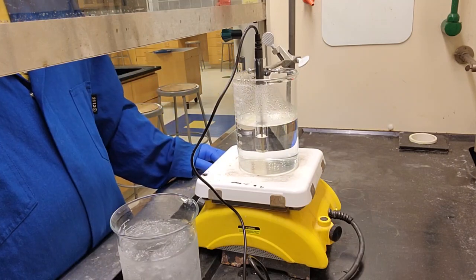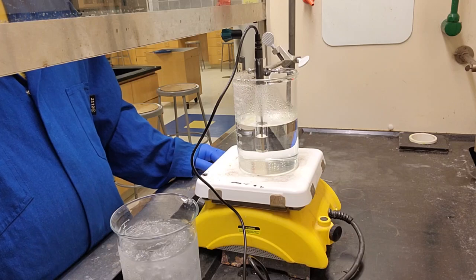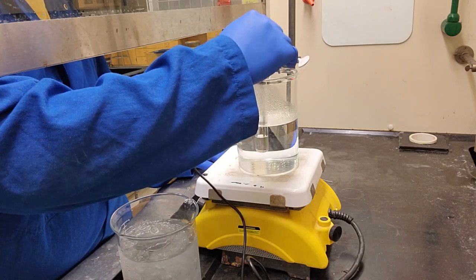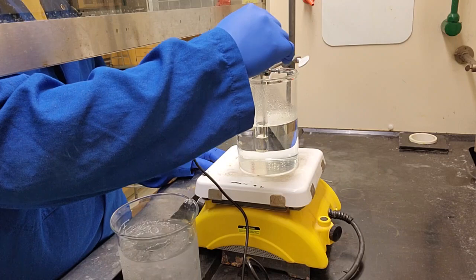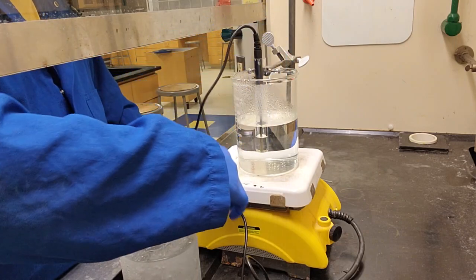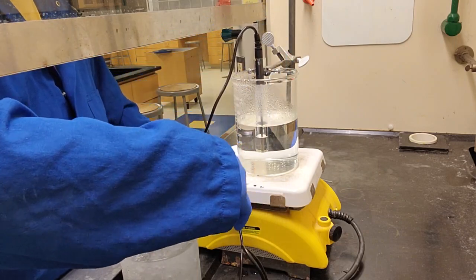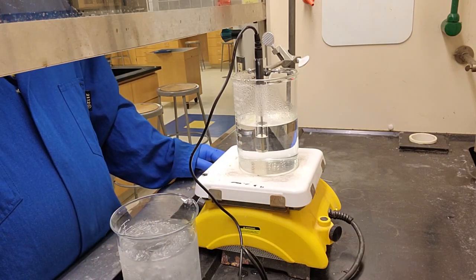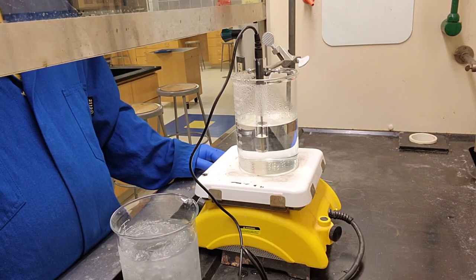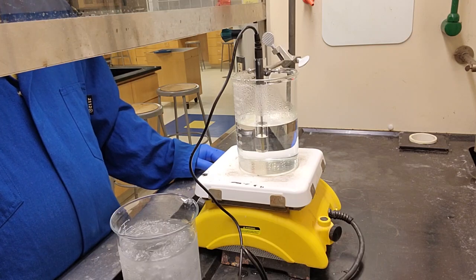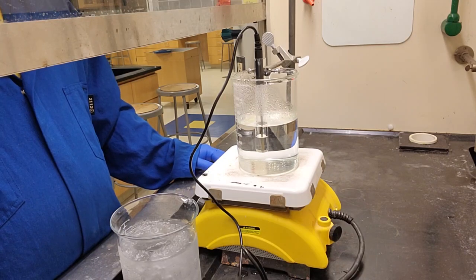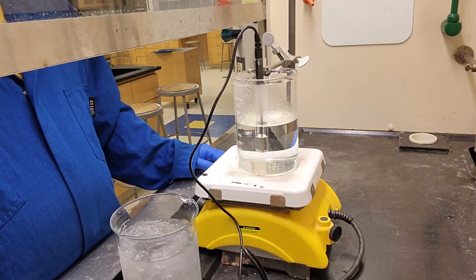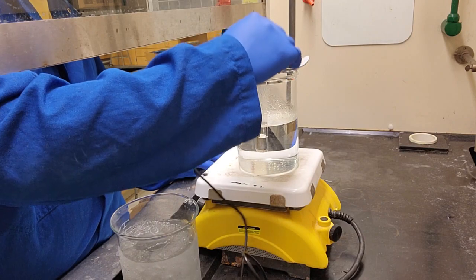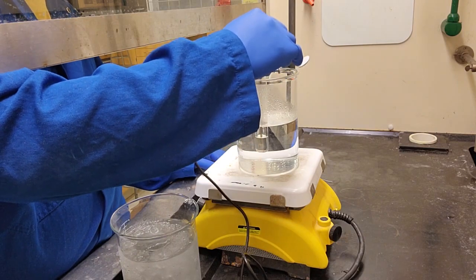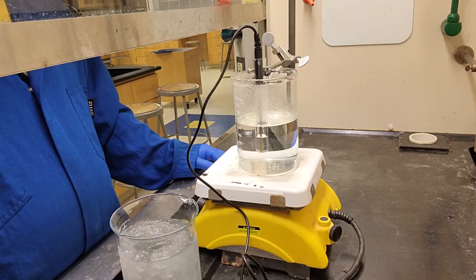So the first reading will be the menthol, and second, you need to have this up and down motion, because some people just leave the probe like this inside the menthol through the whole process, and that will cause you to only read that one point, which might make it inaccurate. Our purpose is to have a really good reading of the temperature change in the menthol. With this up-down motion, you can obtain more data through the menthol sample.